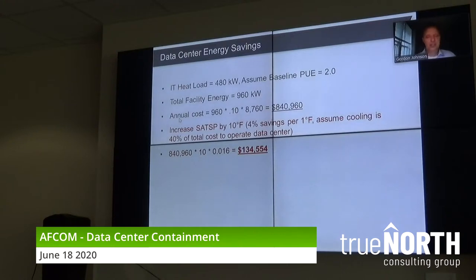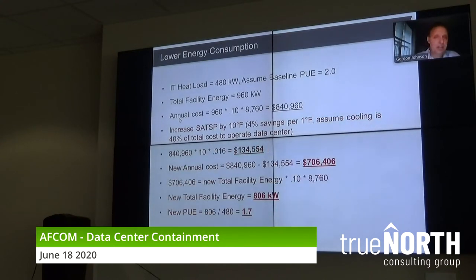I'm not trying to get too crazy here with our math, but I like to say for every degree you raise your temperature, you should see 1.6% savings on the overall cost to operate your data center. It may be higher than that. We don't like to surprise people. I don't want to say you're going to save $300,000 and you only save $134,000. We want to make our customers happy. If they wind up saving more, that's fantastic. $840,000 times 10 degrees times 1.6% says you're going to save $134,000 operating this data center.